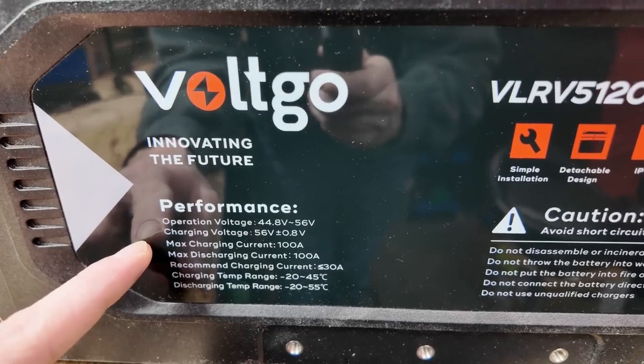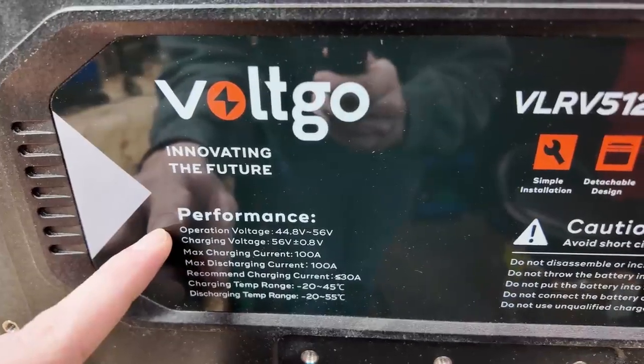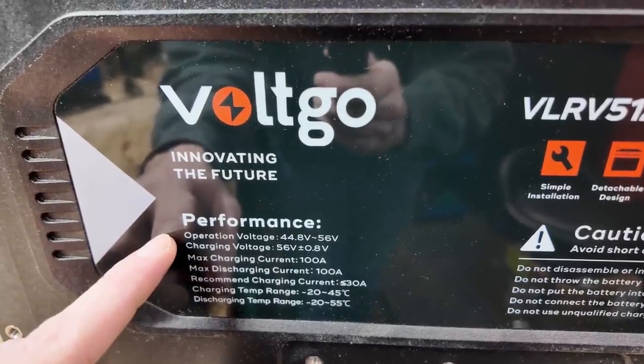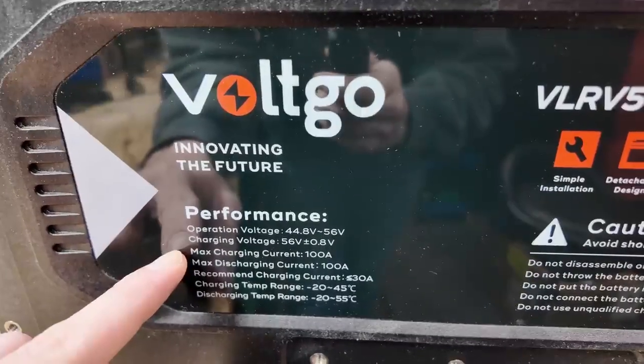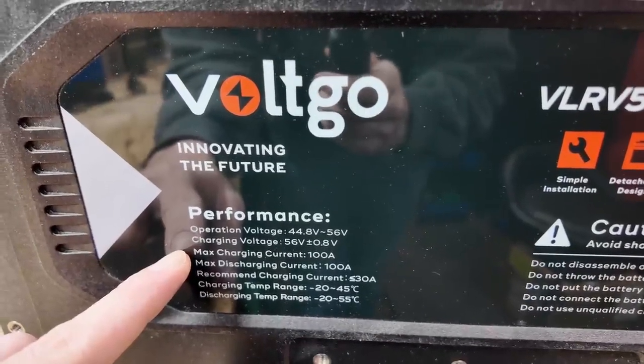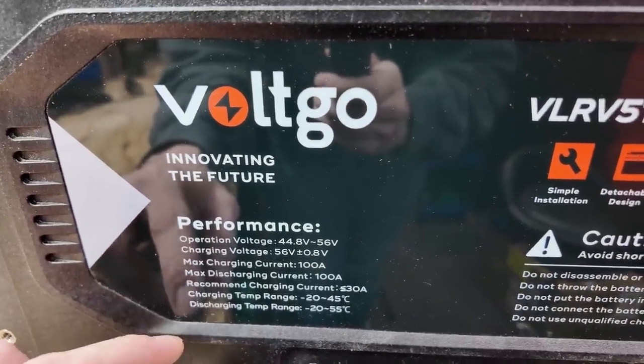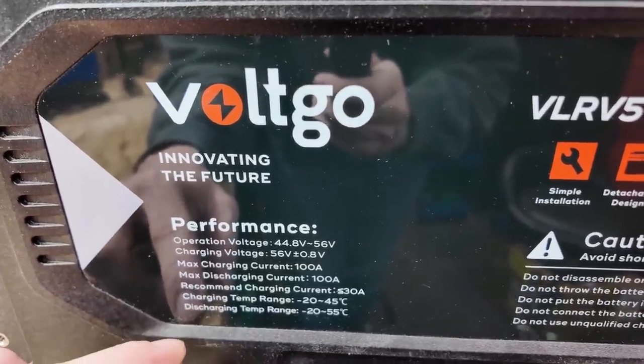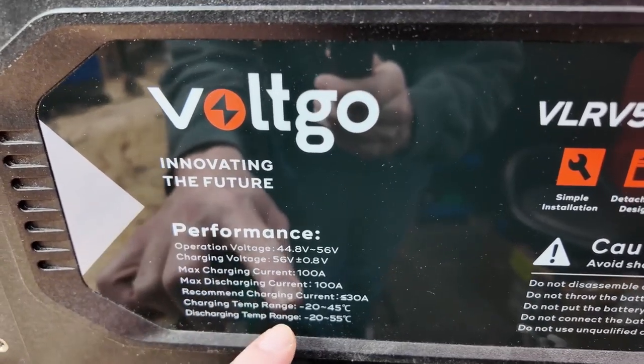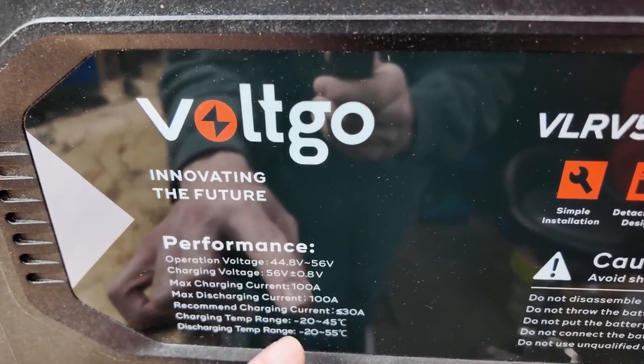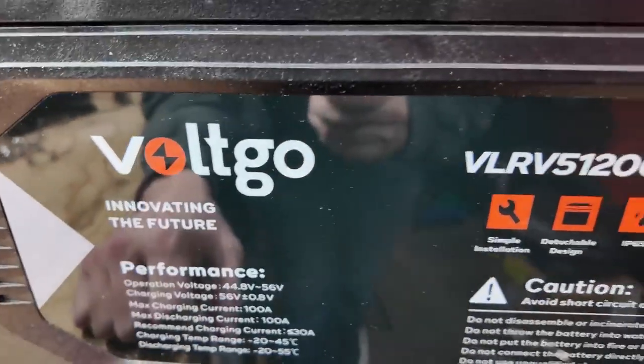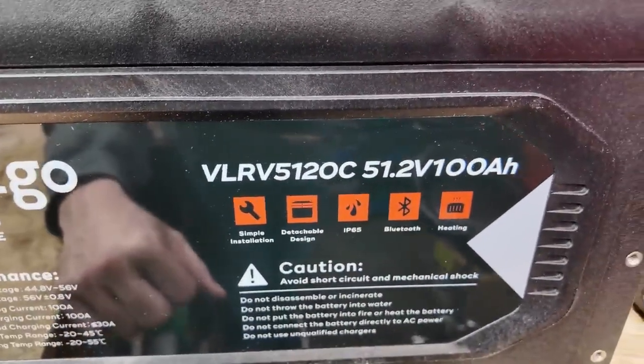Now some of the stats on this battery. We have operating voltage 44.8 to 56 volt, charging voltage, maximum charging current of 100 amps, maximum discharging current of 100 amps, recommended less than 30. Charging temperature range minus 20 to 45 degrees because this battery is heated. And this is the 48 volt model.